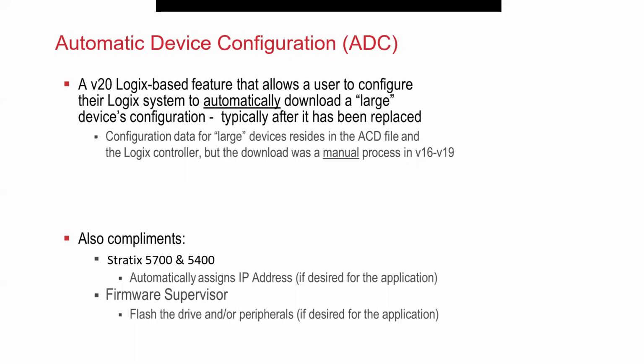I always get the question, do I have to use a managed switch for ADC to work? My answer to that truthfully is, no, you don't. But you will then have to manually, which is not hard at all, assign the IP address to the drive that you're replacing.